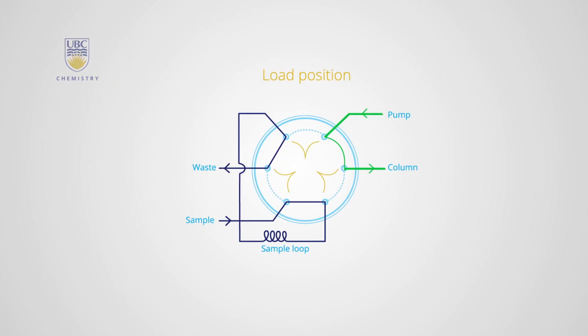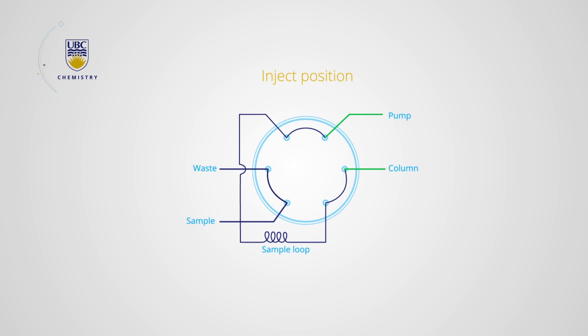Once the position of the loop is switched to the inject position, the mobile phase is directed through the sample loop, thus carrying the sample to the column.